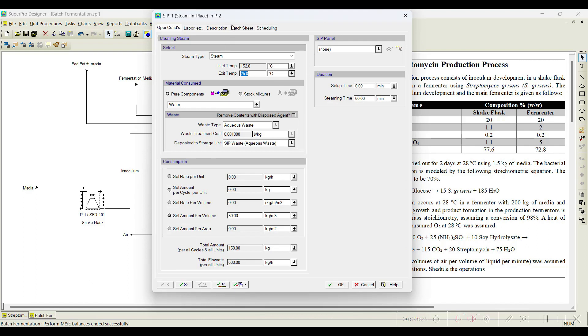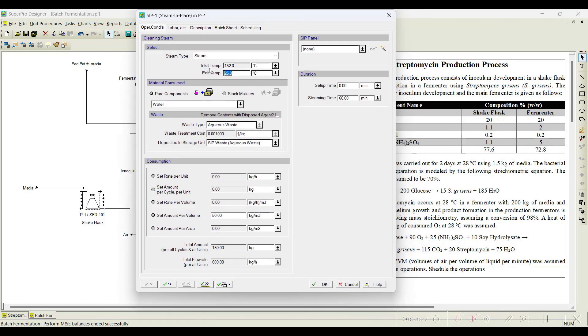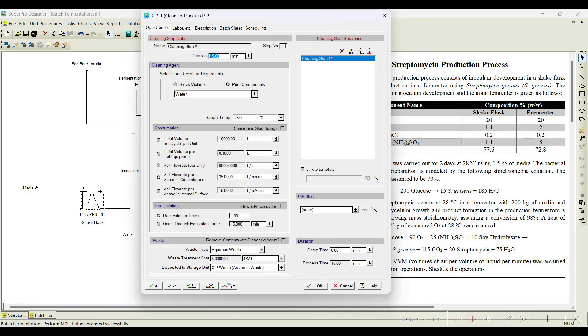Click Yes and let us go to steam in place. We set it so: steam in place — the inlet temperature is 152 degrees and the exit temperature of the steam entering and exiting is 25 degrees Centigrade. Let us go with all default values. I will steam it for around 10 minutes, and the flow rate and other things we just go with default. You can notice the steam component is pure water by default. If you are steaming with any other component — for example sometimes we use WFI water — you can select it here.